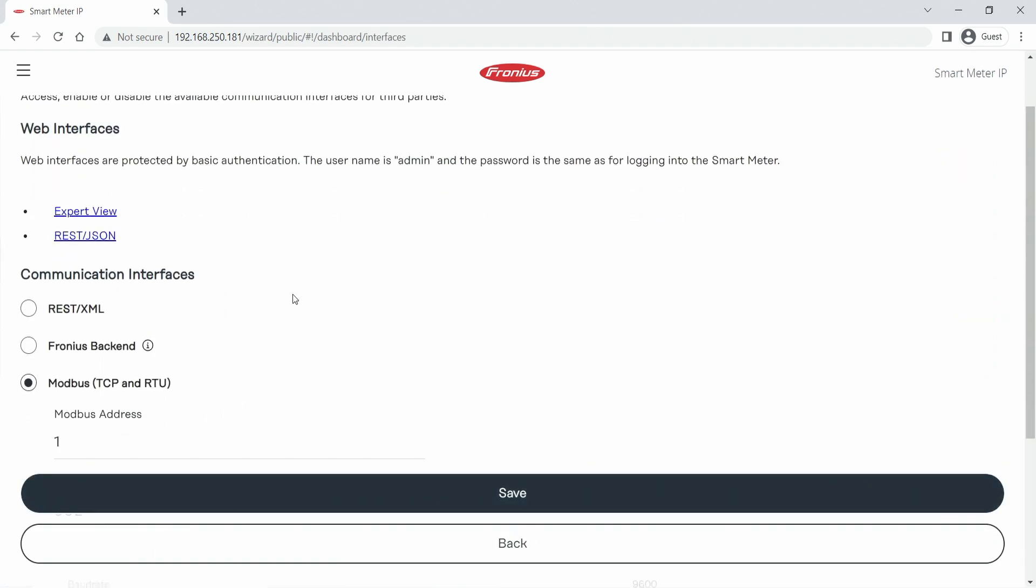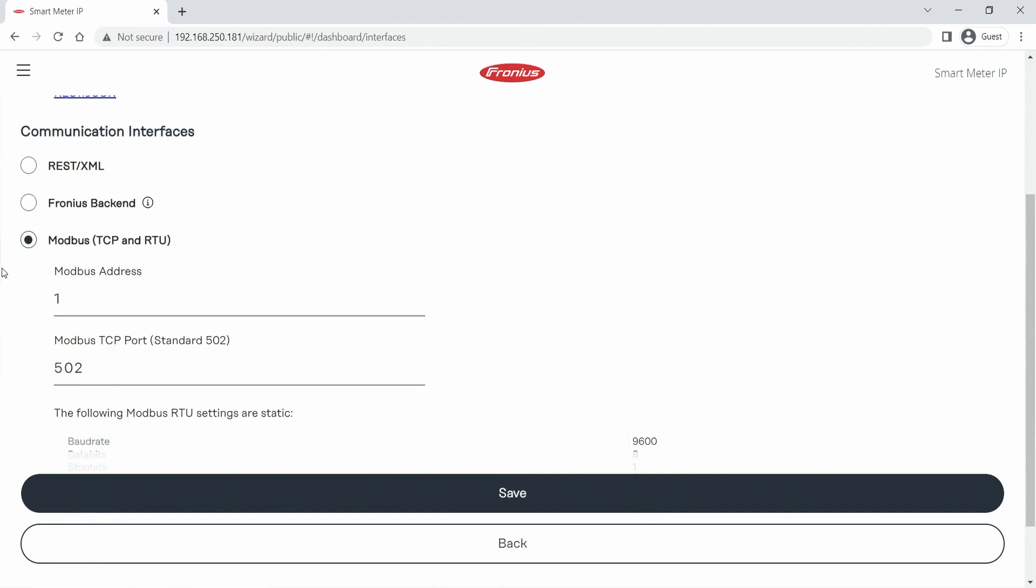With this little symbol here we can click on it. It opens up a submenu, and if we scroll down further we can see or select Modbus TCP and RTU, and here it's very easy to change from the standard 1 to number 2 or 3.